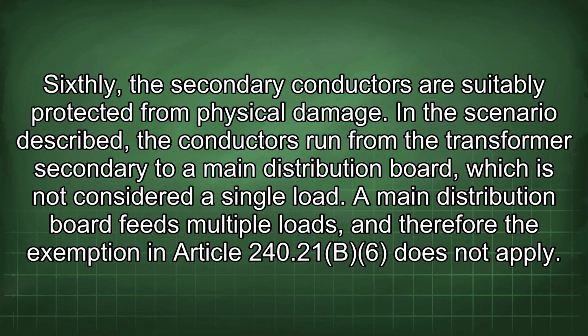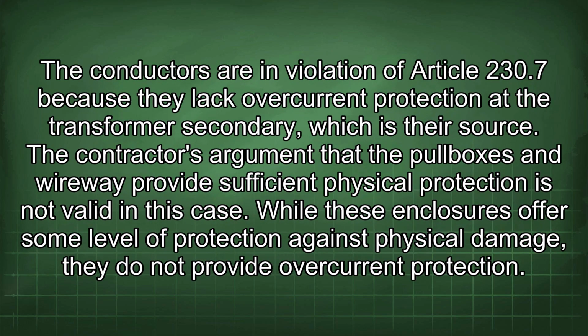In the scenario described, the conductors run from the transformer secondary to a main distribution board, which is not considered a single load. A main distribution board feeds multiple loads, and therefore the exemption in Article 240.21(B)(6) does not apply. The conductors are in violation of Article 230.7 because they lack overcurrent protection at the transformer secondary, which is their source.